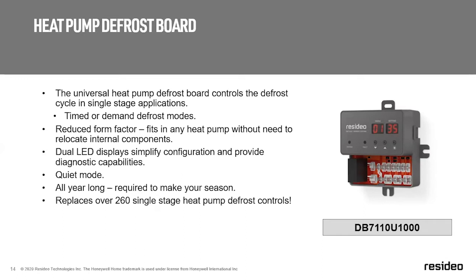And when you start looking at defrosts, there's a good bit of OEMs that just do timed defrost. So it might be going into defrost when you could actually be holding it off from doing so and doing it on a demand basis. So you could upgrade from a timed-only defrost board to one that can do timed or demand. That way we're running defrost less, potentially, and saving energy. For troubleshooting, you can force this unit into defrost by holding in a button on the device, which is great for your tune-up technicians or even your service techs.